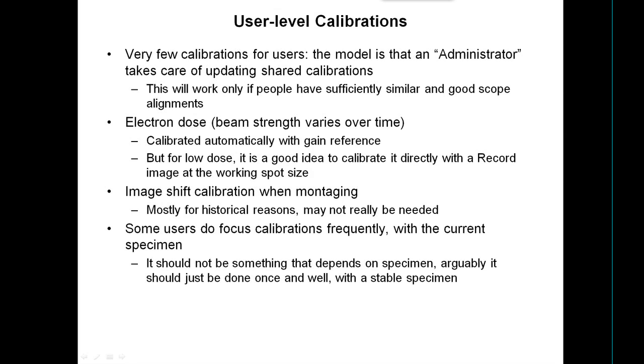The montaging routine always asks you to calibrate the image shift. It's not certain this is always needed — it definitely used to be needed on older microscopes — and it may matter more on JEOL than FEI, but it can't hurt and it's a quick procedure. Some people also redo focus calibrations frequently, which is more than might seem necessary, though it's better to do it with a stable specimen rather than the one you're trying to work with.